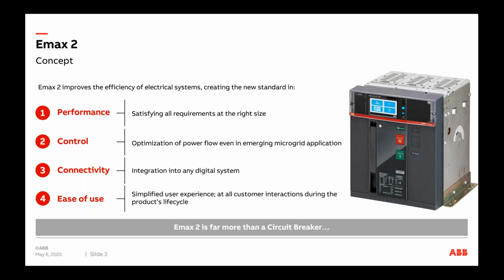Connectivity uses universal protocols of connection and communication. Plug-and-play devices are used to connect onto the breaker, not just to behave as a power distribution circuit breaker, but also behave as a brain for, let's say, a low voltage switchboard. And then there's the ease of use. So how easy it would be to use the breaker to ensure that we are able to extract all kinds of historicals or current measurements, or if there is a trip or fault or alarm, then to understand what's really happening in the system. The breaker allows us to do that quite clearly and easily.